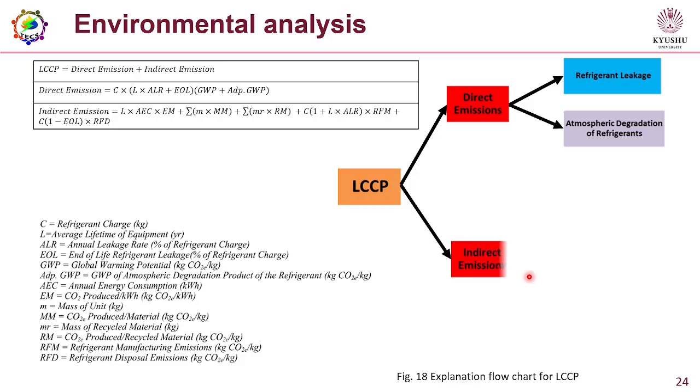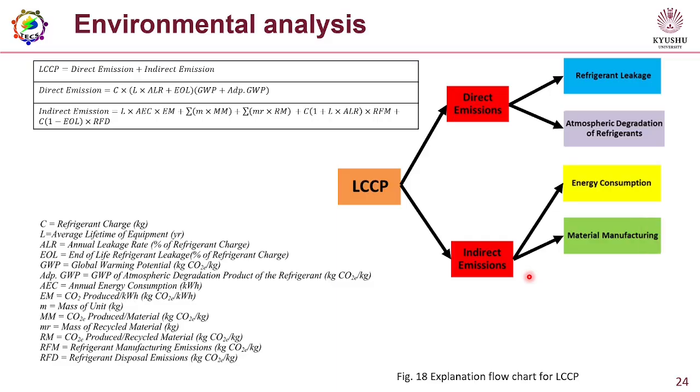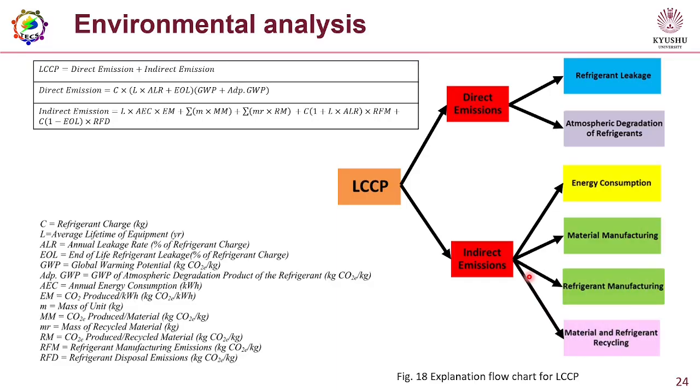So, for the environmental analysis, LCCP was performed. LCCP stands for Life Cycle Climate Performance and it consists of direct emissions as well as indirect emissions. In the direct emissions, it counts the refrigerant leakage as well as atmospheric degradation of refrigerants.